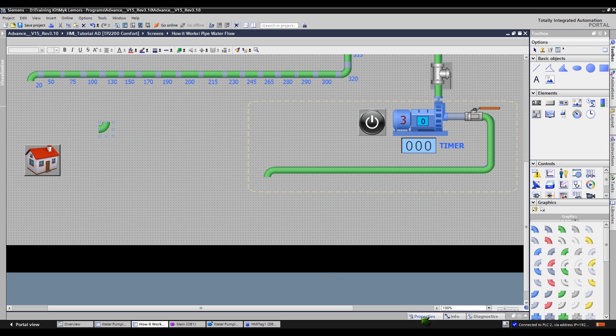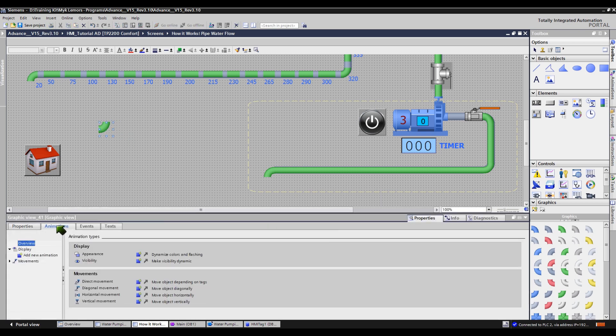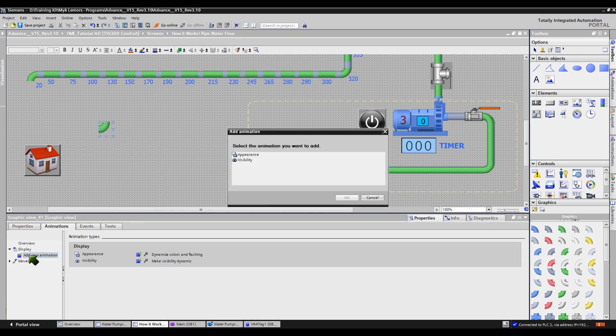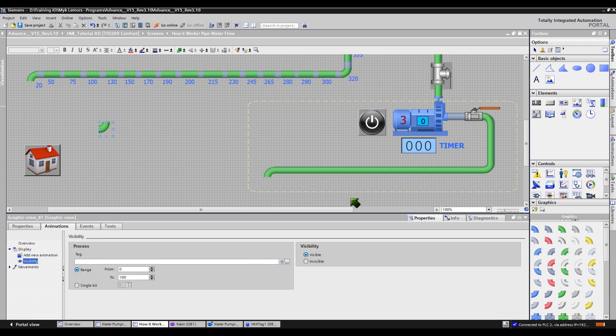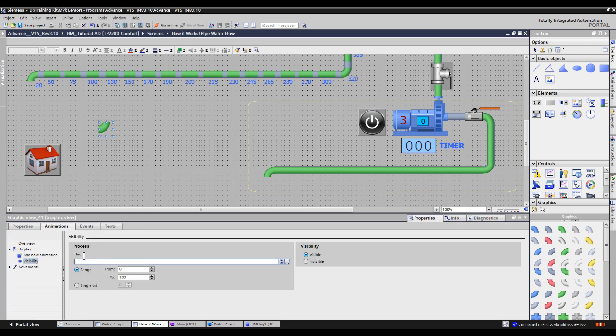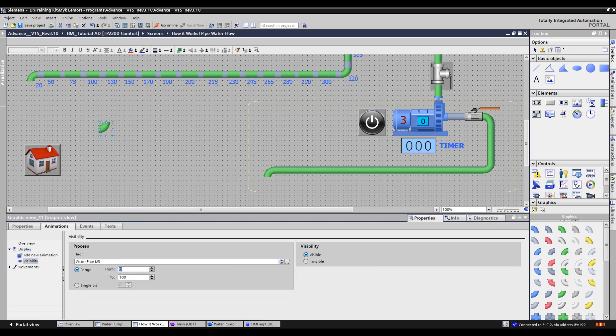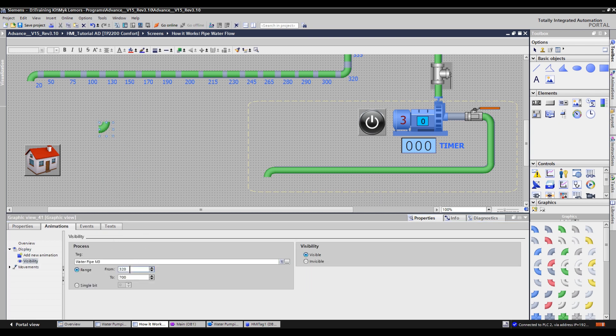Let's set a visibility process tag and process range for this elbow. Switch to the animations tab to create an animation display, then click add new animation. In the displayed dialog box, select visibility and click the OK button. Let's copy the process tag from the other green pipes and set the range from 320 to 700. In our setting, when the water pipe M3 tag starts processing, this elbow will be visible from 3.2 seconds to 7 seconds.